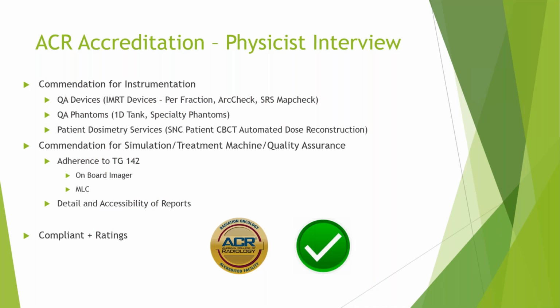And I have to say, having the SunCHECK system and all the devices was a huge benefit for us during our recent ACR reaccreditation survey. Within the physics interview, they gave us commendations for the QA devices, QA phantoms, and patient dosimetry services, as we use the cone beam dose reconstruction on cone beam as an in vivo monitor.